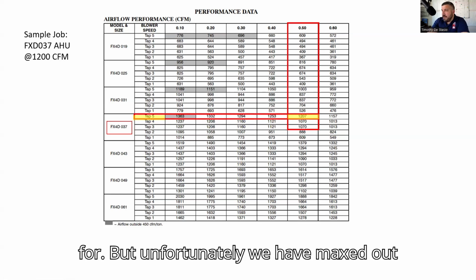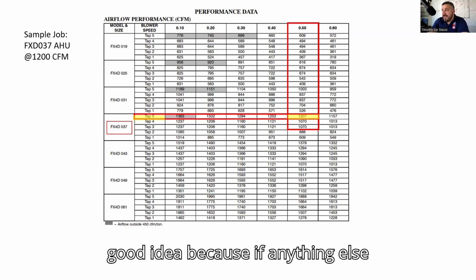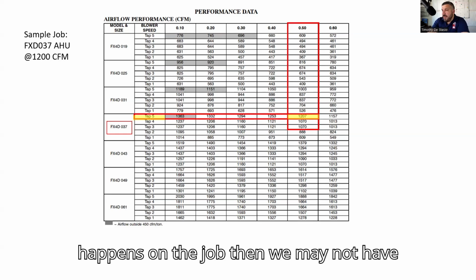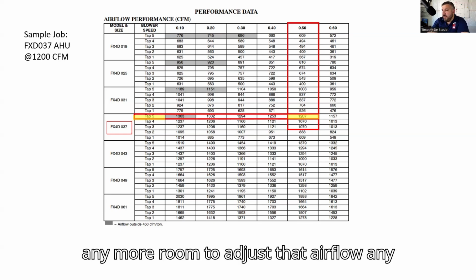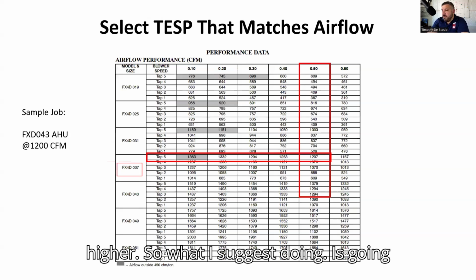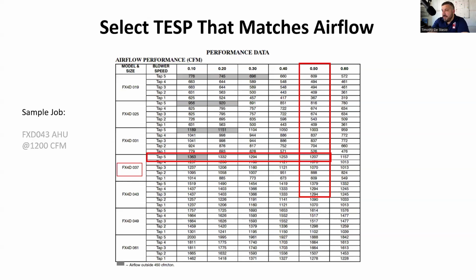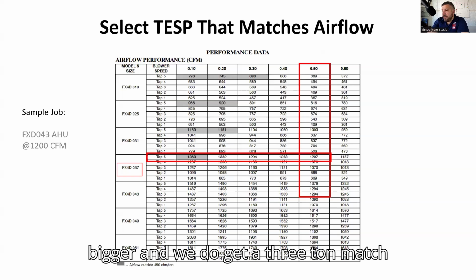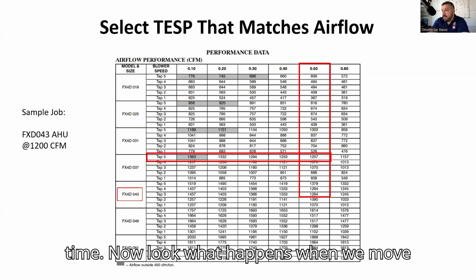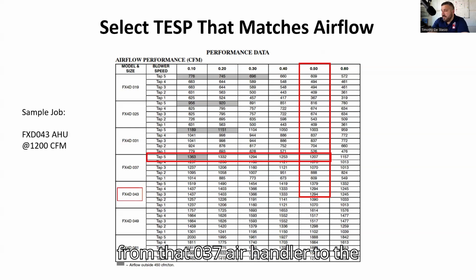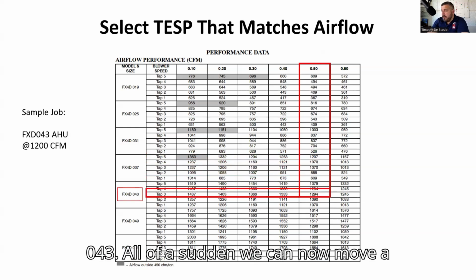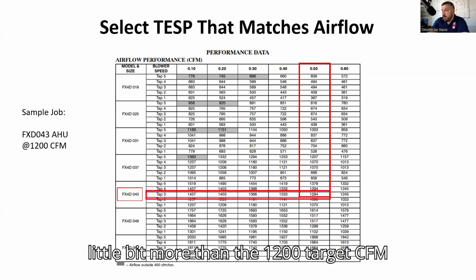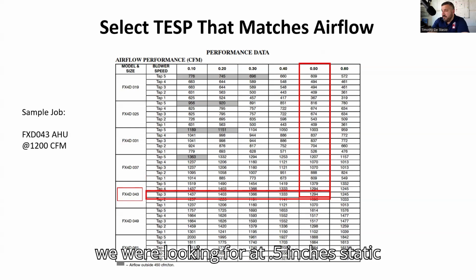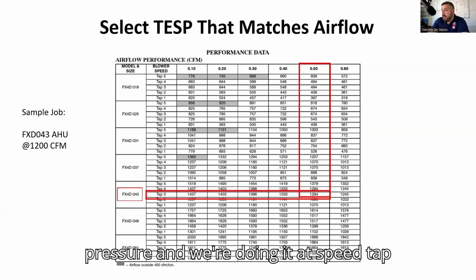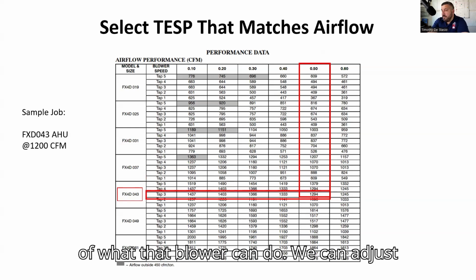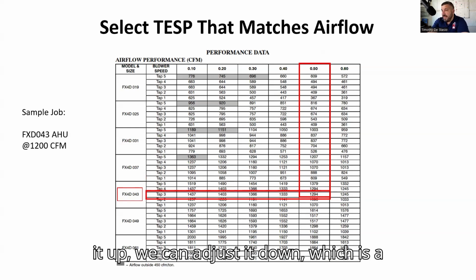But unfortunately, we have maxed out this air handler. That may not be a good idea because if anything else happens on the job, then we may not have any more room to adjust that airflow any higher. So what I suggest doing is going with maybe the next air handler bigger. And we do get a 3-ton matchup with 3.5-ton air handlers all the time. Now look what happens when we move from that 037 air handler to the 043. All of a sudden we can now move a little bit more than the 1200 target CFM we were looking for at 0.5 inches static pressure, and we're doing it at speed tap 3. So we're right there in the middle of what that blower can do. We can adjust it up and we can adjust it down, which is a really good thing.